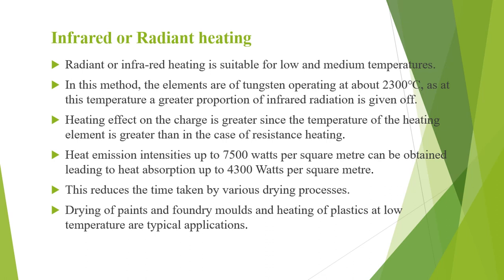Infrared or radiant heating: in resistance ovens the heat is transferred from the heating elements to the charge partly by radiation and partly by convection, the latter predominating at low and medium temperatures. In infrared or radiant heating, the heating elements are made of tungsten and operate at about 2300 degrees Celsius, at which a greater proportion of infrared radiation is given off. The heat emission intensity of up to 7500 watts per square meter is obtained, leading to heat absorption of up to 4300 watts per square meter, reducing the time taken by drying processes. Applications are drying of paints, foundry moulds and heating of plastics at low temperature.